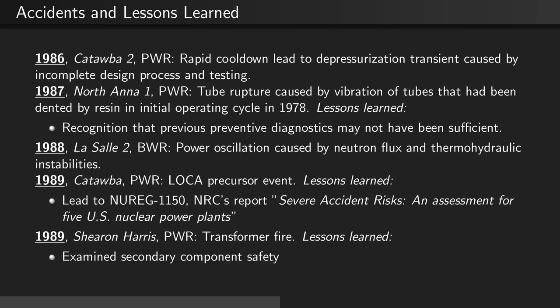In 1989, at Shearon Harris, a pressurized water reactor, there was a transformer fire. This led to further examination of secondary component safety that weren't directly related to the core or the coolant loops.